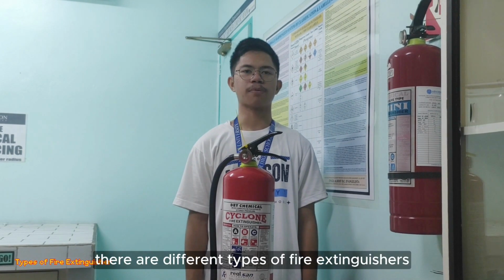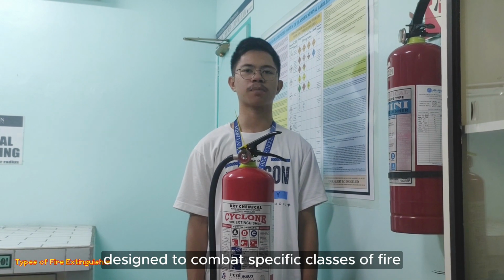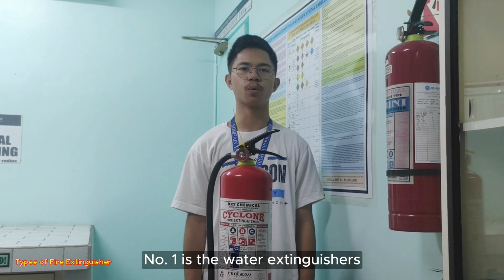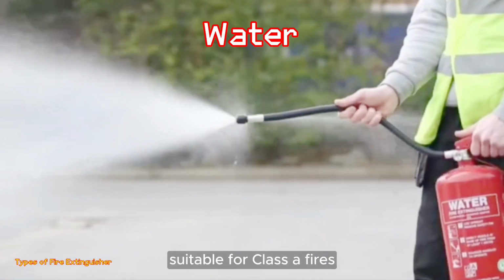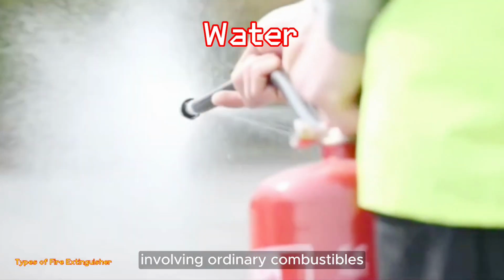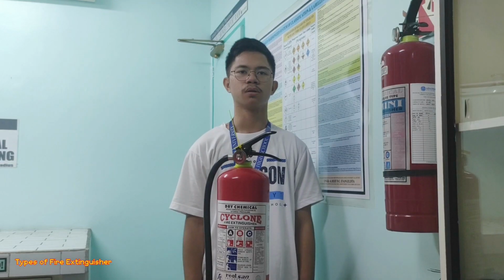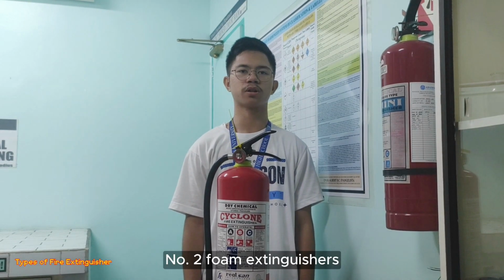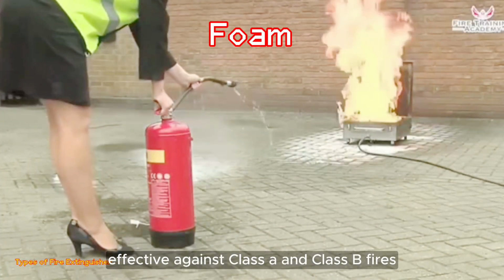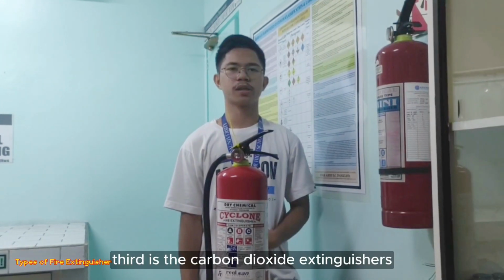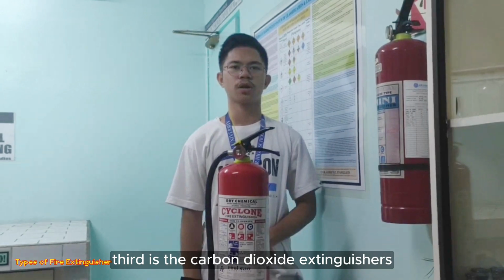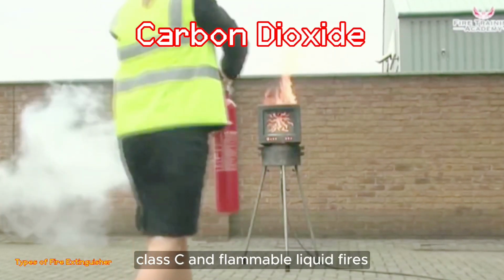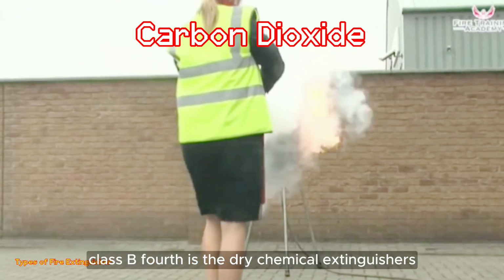There are different types of fire extinguishers designed to combat specific causes of fire. Number one is the water extinguishers, suitable for Class A fires involving ordinary combustibles. Number two, foam extinguishers, effective against Class A and Class B fires. Third is the carbon dioxide extinguishers, used for electrical fires Class C and flammable liquid fires Class B.